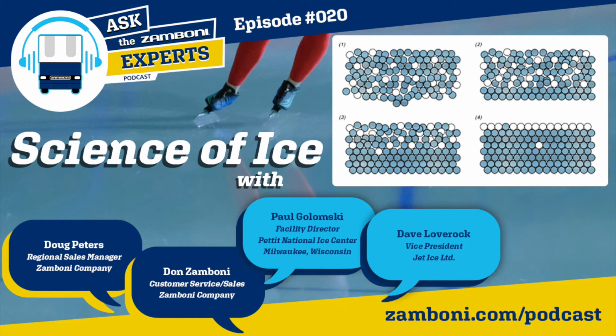So it kind of defeats logic when you think about what we're discussing, how important purified water is, and how it's not energy efficient and it causes cloudiness and all kinds of problems with your ice. We're spending all this money to purify water, and then we're taking that water and sending solid back into it. So it's a strange process, and it's, I think, debatable by all the ice techs out there right now. But I've found a little bit of back blend of solids back into the purified water is helpful in terms of durability and bond of layers together.